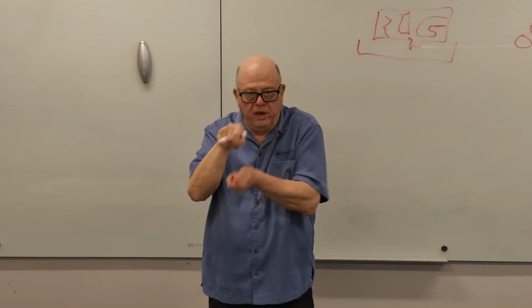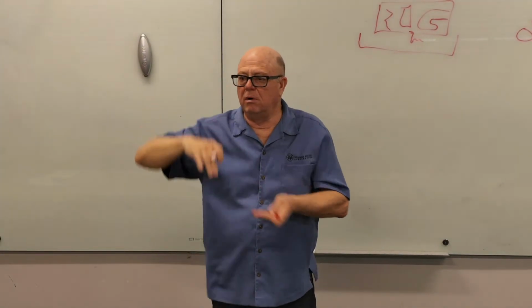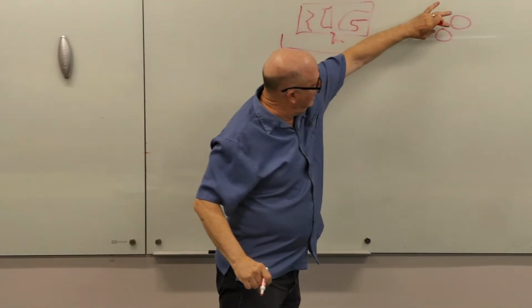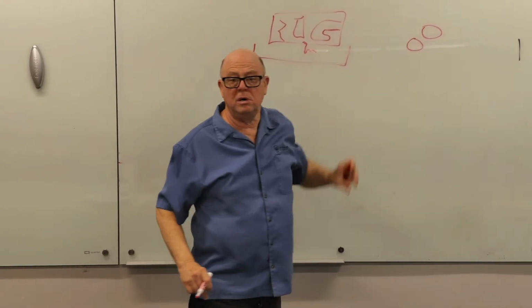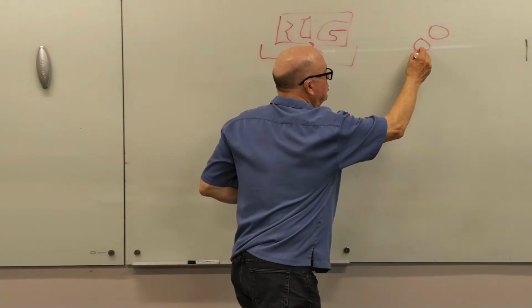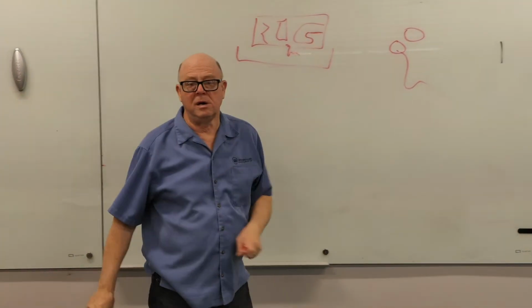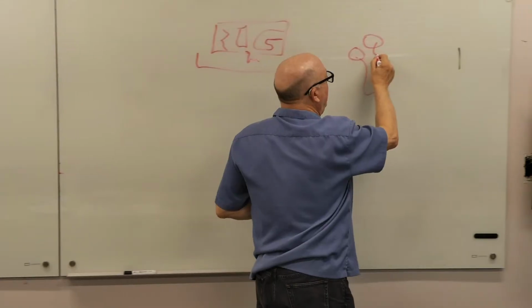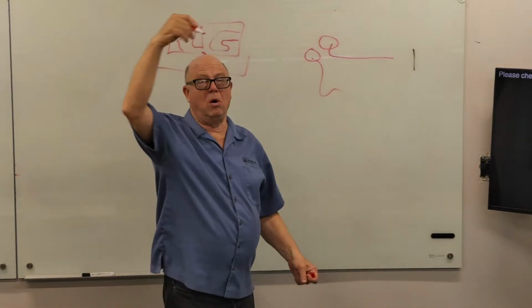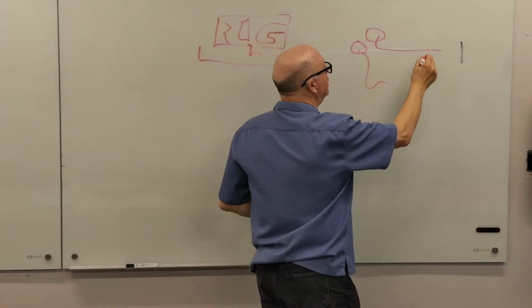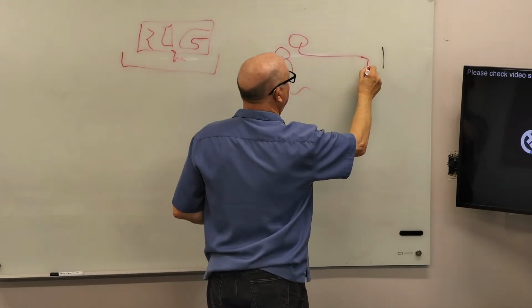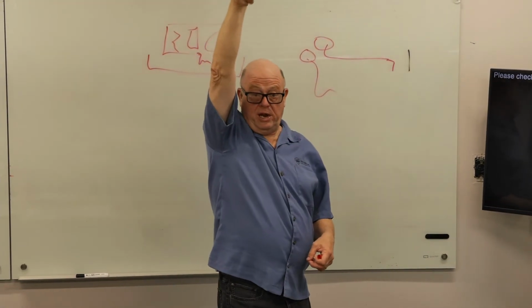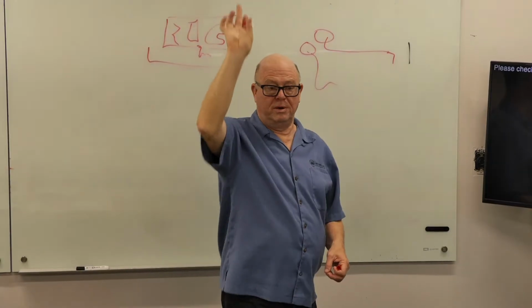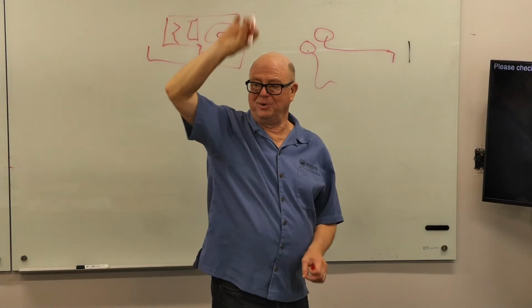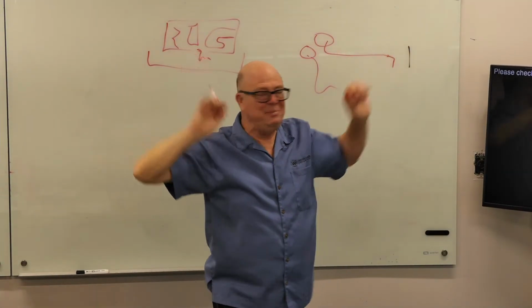There's usually two connections. One's higher than the other, usually by about the diameter of this bottom one and then the next one. So this one goes to your P-trap and out. This one you pipe someplace visible. Out into a hallway is a great place to put it. You turn it down, you poke it through the ceiling tile, probably have somebody put one of those nice shiny chrome round things around it to make it look pretty.